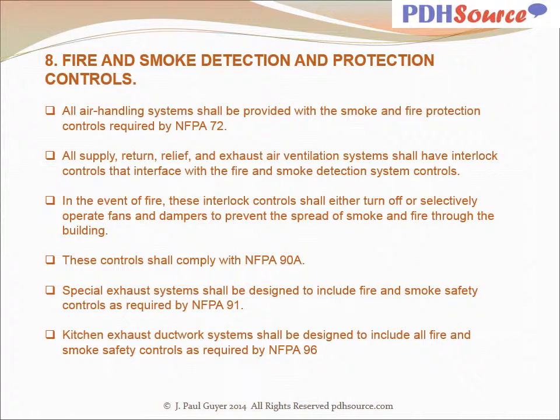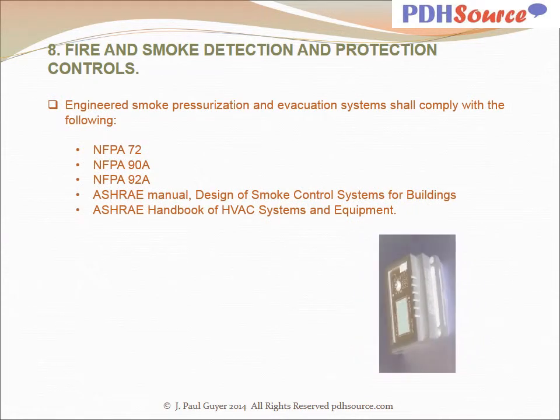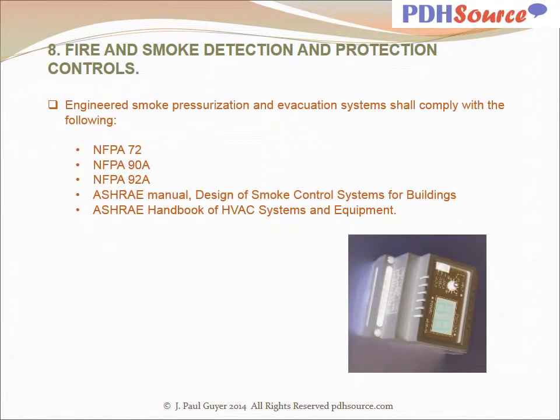Special exhaust systems shall be designed to include fire and smoke safety controls as required by NFPA 91. Kitchen exhaust ductwork systems shall be designed to include all fire and smoke safety controls as required by NFPA 96. Engineered smoke pressurization and evacuation systems shall comply with the following: NFPA 72, NFPA 90A and 92A, ASHRAE Manual, Design of Smoke Control Systems for Buildings, and ASHRAE Handbook of HVAC Systems and Equipment.